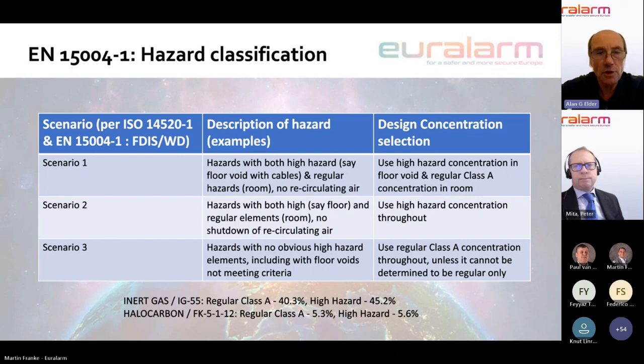In scenario 2, where you have a high hazard classification, for example, the floor, and regular elements in the room, with no shutdown of the recirculating air, you would use a high hazard concentration throughout. If you don't do that, what would happen is that the airflows between the spaces would start to dilute the concentration within the subfloor and in some way increase the concentration within the room. So the guidance is to use the high hazard concentration throughout both of those spaces.